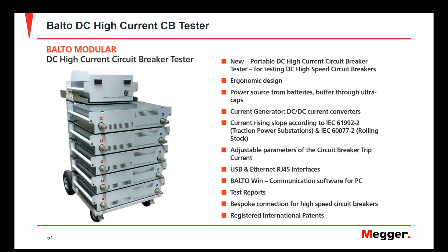Lastly, the Balto DC high current circuit breaker tester is a test set you charge before going out in the field — it operates by battery power assisted by ultra capacitors. It provides a high current DC output for testing DC high-speed circuit breakers, delivering that power-dense output very quickly to test those high-speed circuit breakers within the required time. This instrument is compliant with IEC 61992-2 for testing high-speed DC circuit breakers, and it operates off the Balto Win software for easy user interface and test report production.